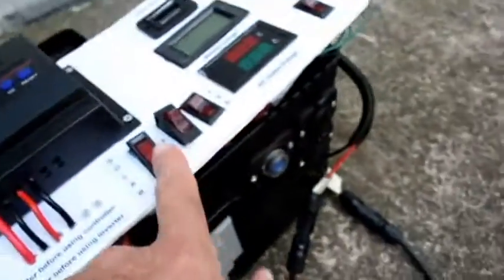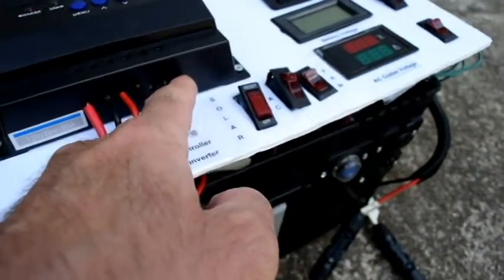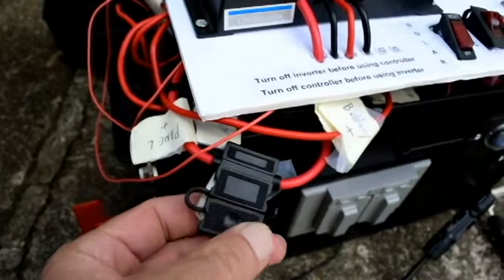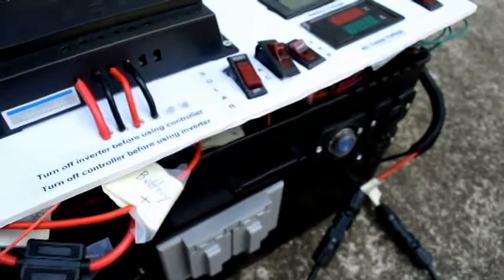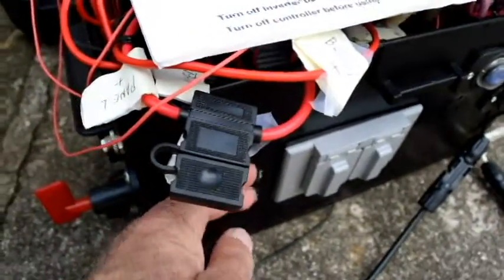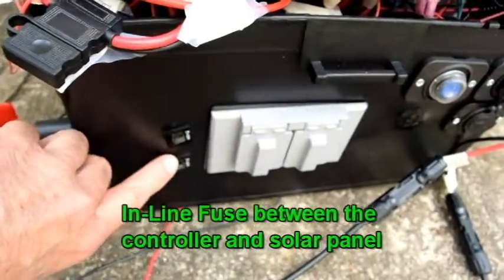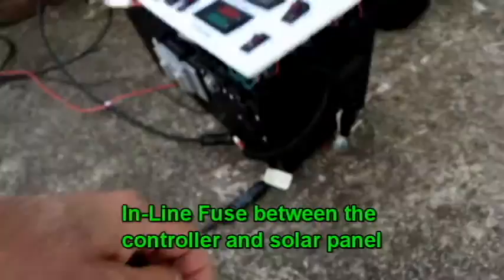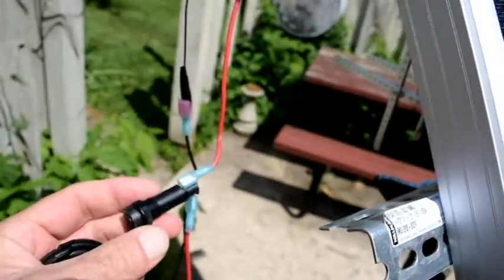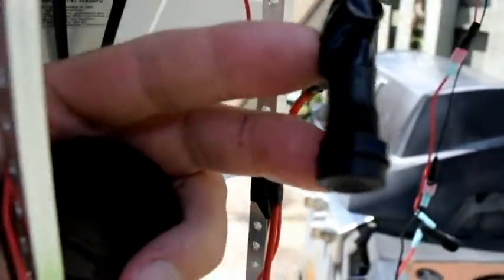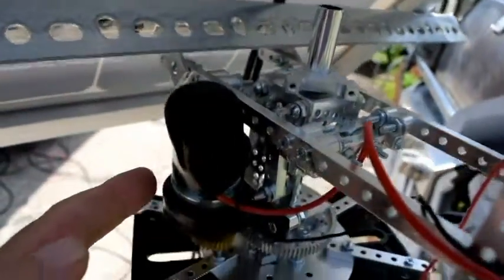I've got a quick disconnect. I've got a circuit breaker between the battery and the inverter. I've got a circuit breaker between the battery and the controller. I've got an inline fuse between the battery and the panel. I've got a circuit breaker for each of the 120 volt outlets. I've got a circuit breaker for the DC outlet. I've got an inline fuse, 3 amp, to the solar tracker circuit, and on the other side I've got an inline fuse from the tracking circuit down to the motor.